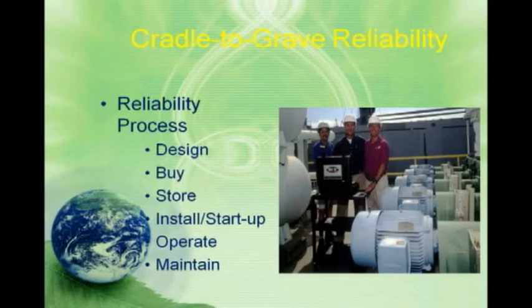An occasional review of the power circuit, the power quality, the stator, rotor, and air gap is going to make sure you get the expected 15 to 20 years of life out of a motor, or longer. And as critical as that, and given the whole green element of this presentation, verify that the efficiency of the motor is optimized, is running where it should be, and that we're not using more power than required to deliver the product that we're trying to deliver.